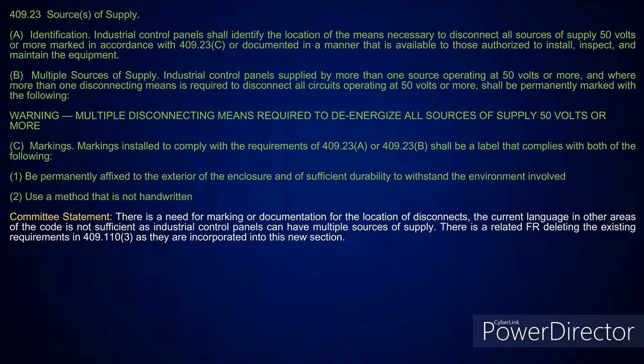Then they also talk to you about the multiple sources of supply, and they tell you they have to be permanently marked that state: Warning, multiple disconnecting means required to de-energize all sources of supply 50 volts or more. And of course, I'll tell you that the markings here cannot be handwritten, and they have to be affixed to the exterior in order to withstand the environment. True. And just to let everyone know, I did do extensive research on this. The labels that come off a label maker are rated to handle an exterior environment. I did do research on that, and a label maker is compliant as long as it says on the label maker tape that it's suitable for the environment.